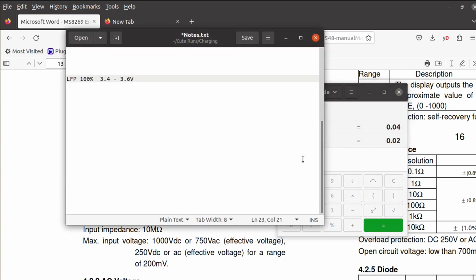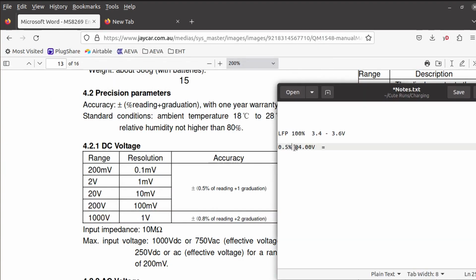So if we go back to our little table here, it was 0.5% of reading plus 1 graduation. If we say 4 volts, that is... what did we say? 0.03 volts - it's plus or minus 0.03 volts. So what that means is that if it's reading 4.00 volts, it could be anywhere between 3.97 volts and 4.03 volts.